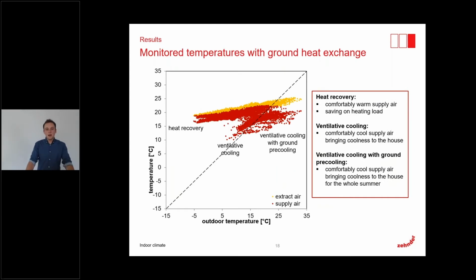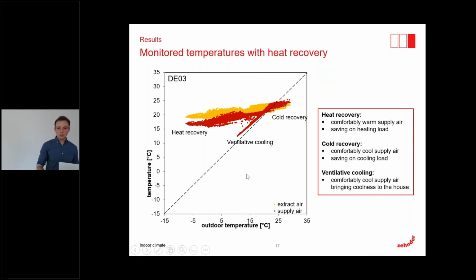So this was the theory, and now we take a look at the results from the field study. It's almost the same graphic. We have the outdoor temperature on the horizontal axis, and on the vertical axis, the inside temperature. The red dots are the values measured throughout the whole year in a 5-minute interval from the supply air. And the yellow dots show the extract air. So what we can see here, oh, sorry, this is the wrong graph. I just wanted to show you the monitored temperatures with heat recovery, but it's the same graphic.